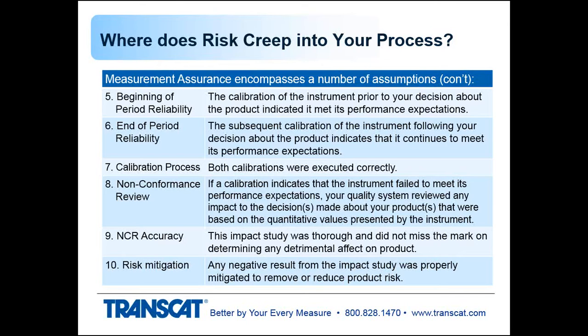And because calibration only has 2 discrete points in time to tell you how the condition of the instrument is set going forward, and the other end of the discrete point in time is how it is received, looking backward over that calendar interval. So that end of period reliability tells you whether it was able to hold its tolerances and gave you good reliable readings for the decisions on the product.